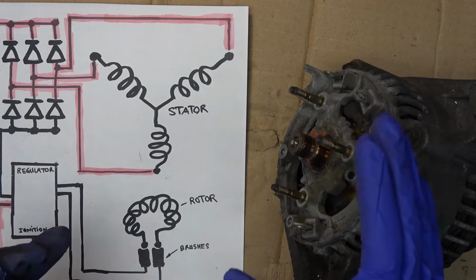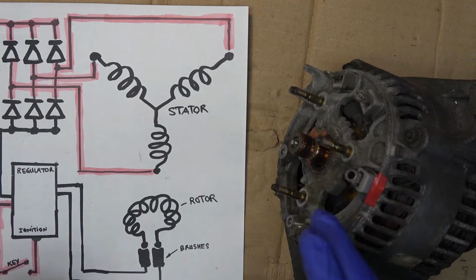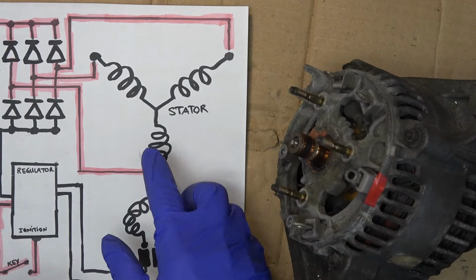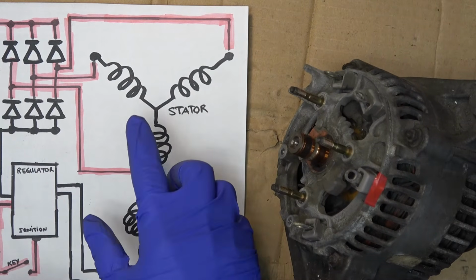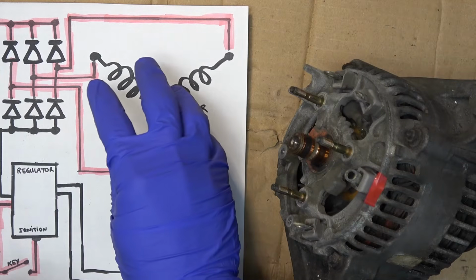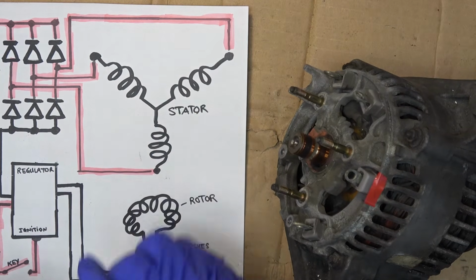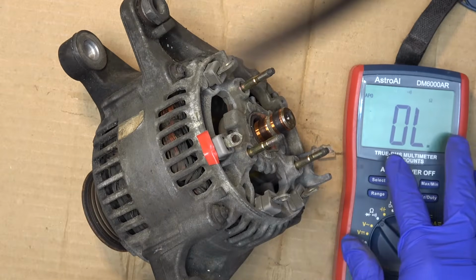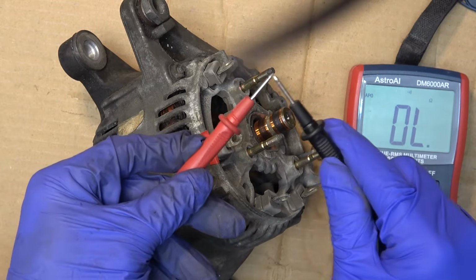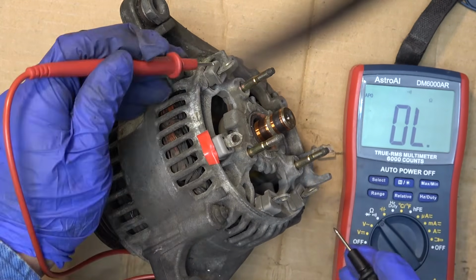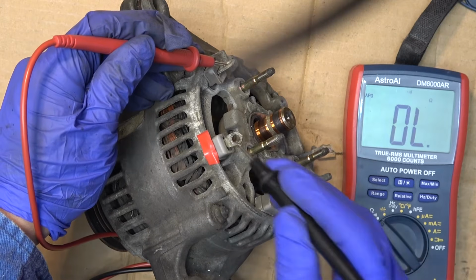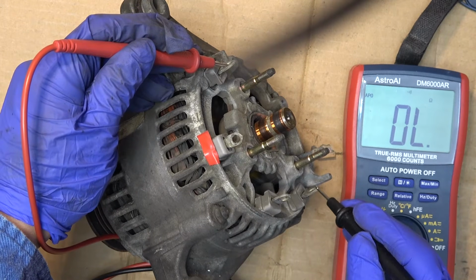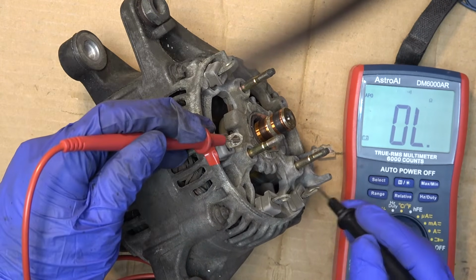The testing procedure is the same. You want to make sure all the windings on the stator are connected together at the midpoint, and that none of them are connected to ground. I'm going to put my meter on continuity test and make sure all the poles are connected together like that.